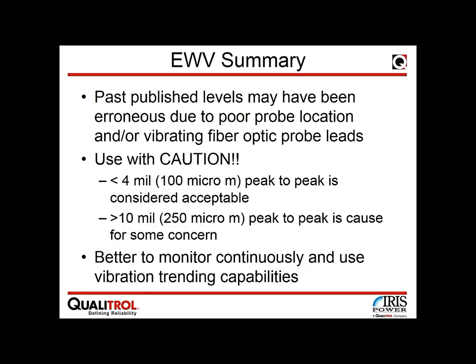Sensors have traditionally been placed on convenient rather than optimal locations, so monitored levels may not reflect actual machine conditions. Guidelines in North America indicate machines should operate at less than 100 micrometers or 4 mils of displacement. If displacement exceeds 10 mils or 250 micrometers, something is moving more than it should. Continuous monitoring is better than periodic inspection, since a periodic approach cannot capture numbers when the machine is hot and at full load.